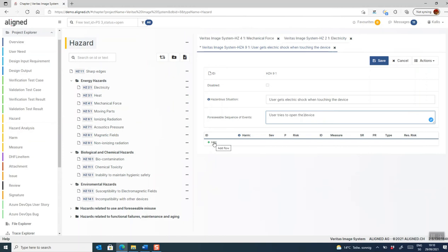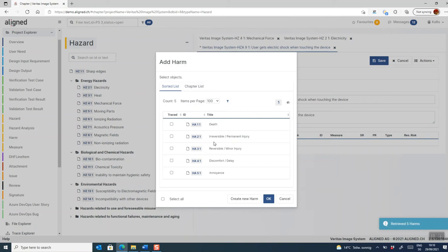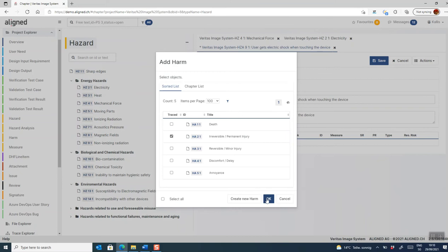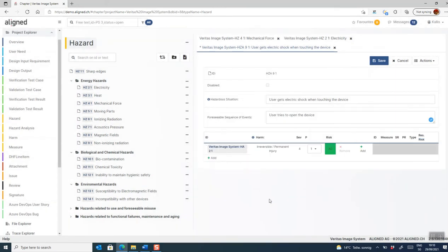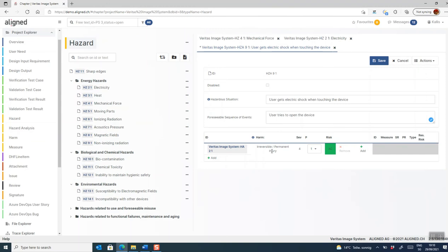I click on this add button to get access to a number of harms that I've already predefined. And they are to be found under the harm category here. And you can add your own harms. I will select this harm, permanent injury. We can see that it's loaded and it's automatically associated with a given severity. So this is written inside the harm item. So every time we select this particular harm, we always get the same severity.